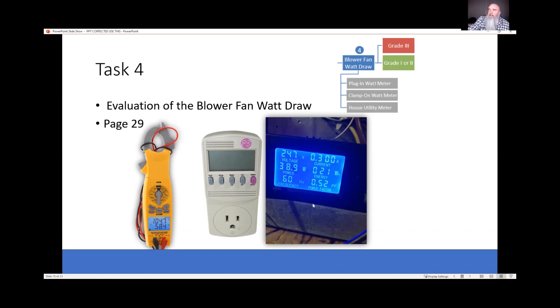The process, and somebody commented variable speed blower, high static, higher wattage. That's true. One of the things that we want to be very specific about when we talk about those types of fans is while the amp draw goes up substantially, the wattage doesn't. And I want to say those motors are nothing short of magic, and they're not. It's just the electronically commutating part. They're able to do more work with less energy consumption. And I'm going to stop there. It's another topic that if I was allowed, I would have you here till 3 o'clock. So I'm not going to do that.